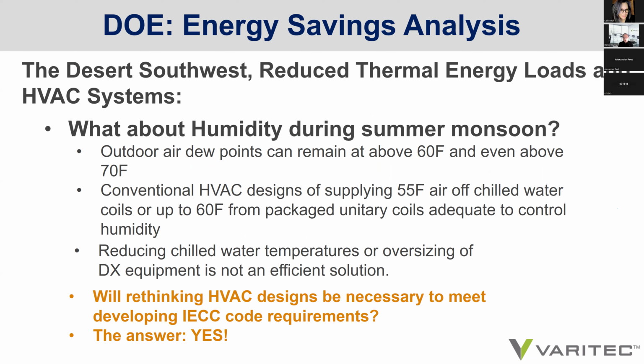And then we can speak to that at a future presentation, of what dew point depressions are available when air is achieving 55 degrees off of a cooling coil. And I think we'll find that a leaving air condition of 52 to 50 degrees might be more appropriate, with a lower supply air dew point, to stabilize humidity infiltration and gain within the more efficient buildings that are being served by less airflow.